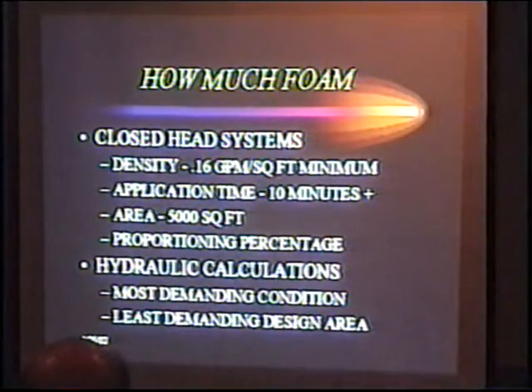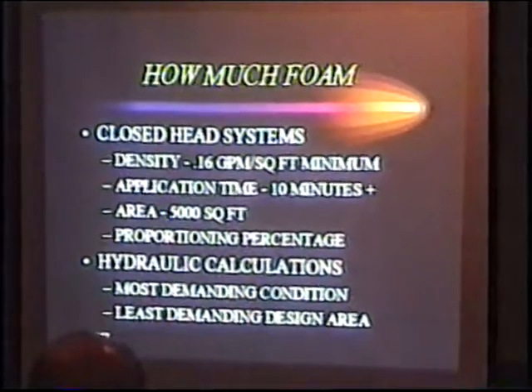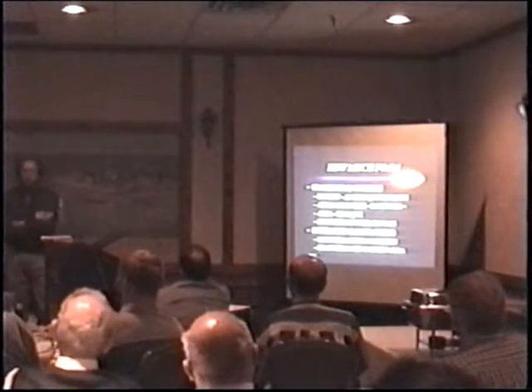Application time, again, minimum of 10 minutes. But we're seeing a number of systems at 15, 20, even 30, depending on the carrier and the situation. Design area, that's all over the board. 5,000 is what NFPA 16 calls for. Closed head systems, well, if you go in an airplane hangar, you're going to have up to, I think, 15,000 square feet per zone. And proportioning percentage, 9 times out of 10, is going to be 3%. Occasionally, again, you see the 1%.